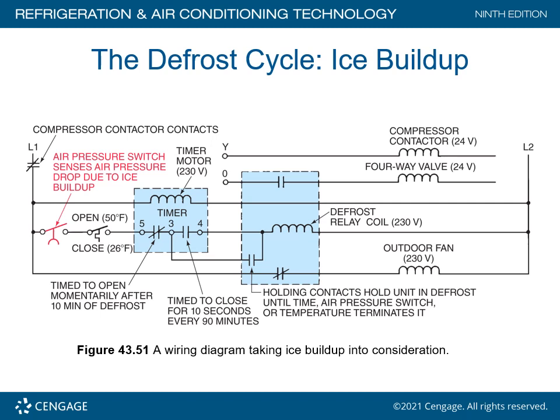Once we put the unit in defrost, we have a minimum time that we allow the unit to stay in defrost. We do not want it to stay in defrost for a long period of time. The electronic board has a selector switch that you move a pin on, or set, when you are doing the setup on the heat pump, and that will limit the amount of time the unit is in defrost during an hour. In other words, one defrost cycle an hour, maybe one defrost cycle in 4 hours, depending on the selections that are made when the unit is installed and commissioned.